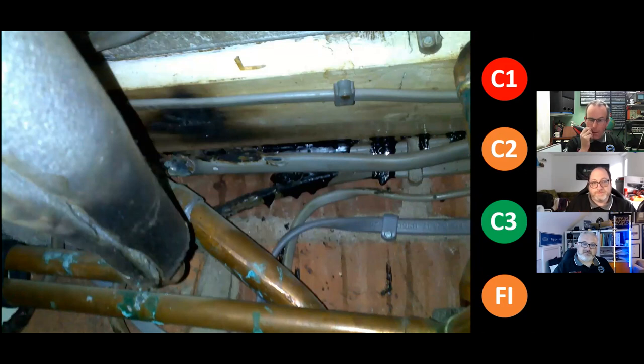You can see where the plumber has obviously done his joints on his copper pipe, and pretty much melted the sheath. I think that was a shower circuit, if I remember rightly. You can also see what looks like pitch, which is leaking from above it. I'd be interested to see what's above that. I never got the photo above. It was what we found underneath. But again, it's one of the common problems that sparks have. It's just rubbish, really, to be honest with you. It's just lazy, sloppy plumbers.